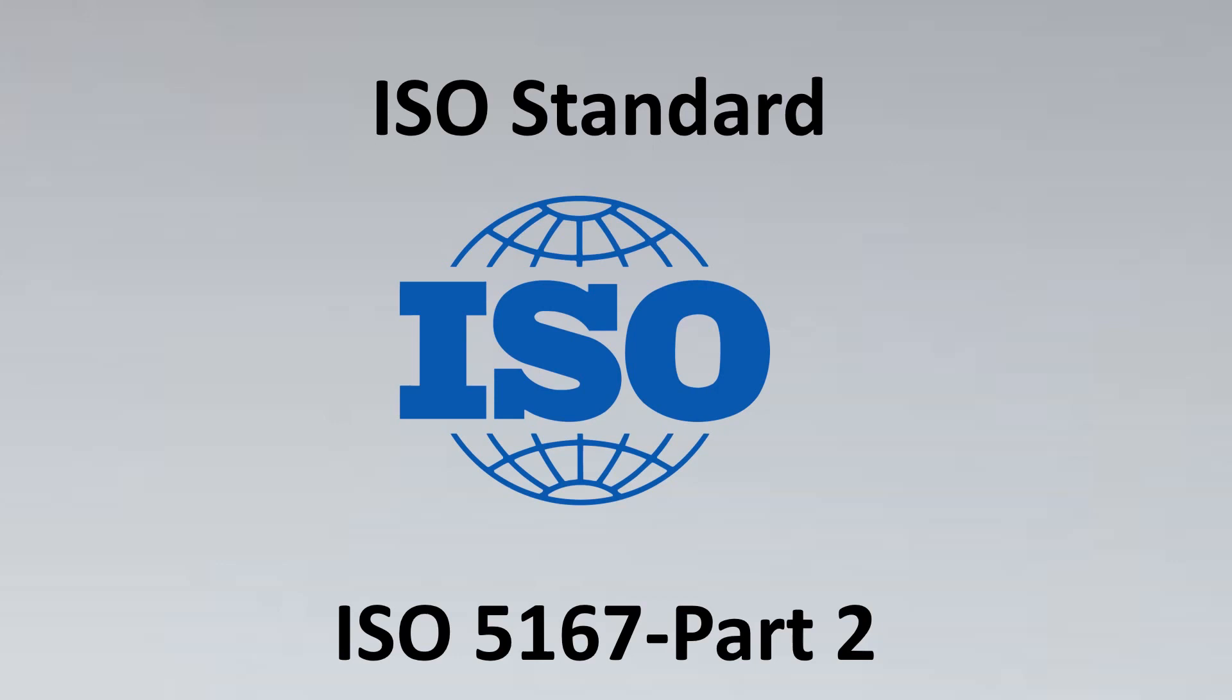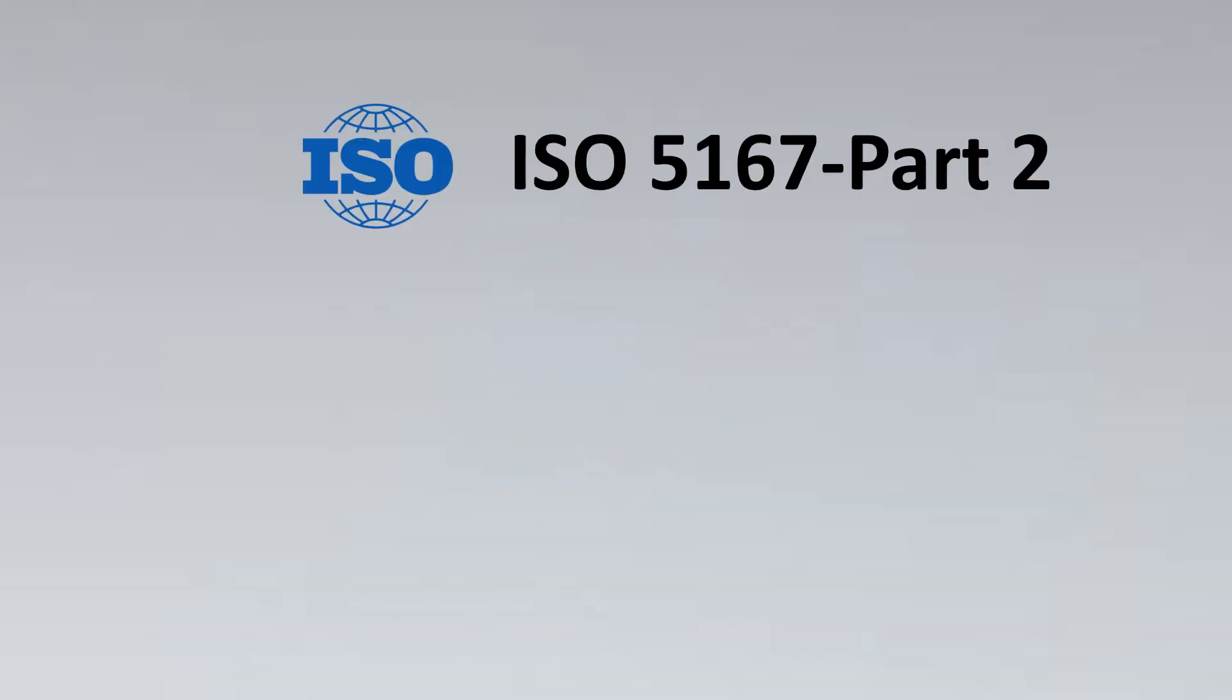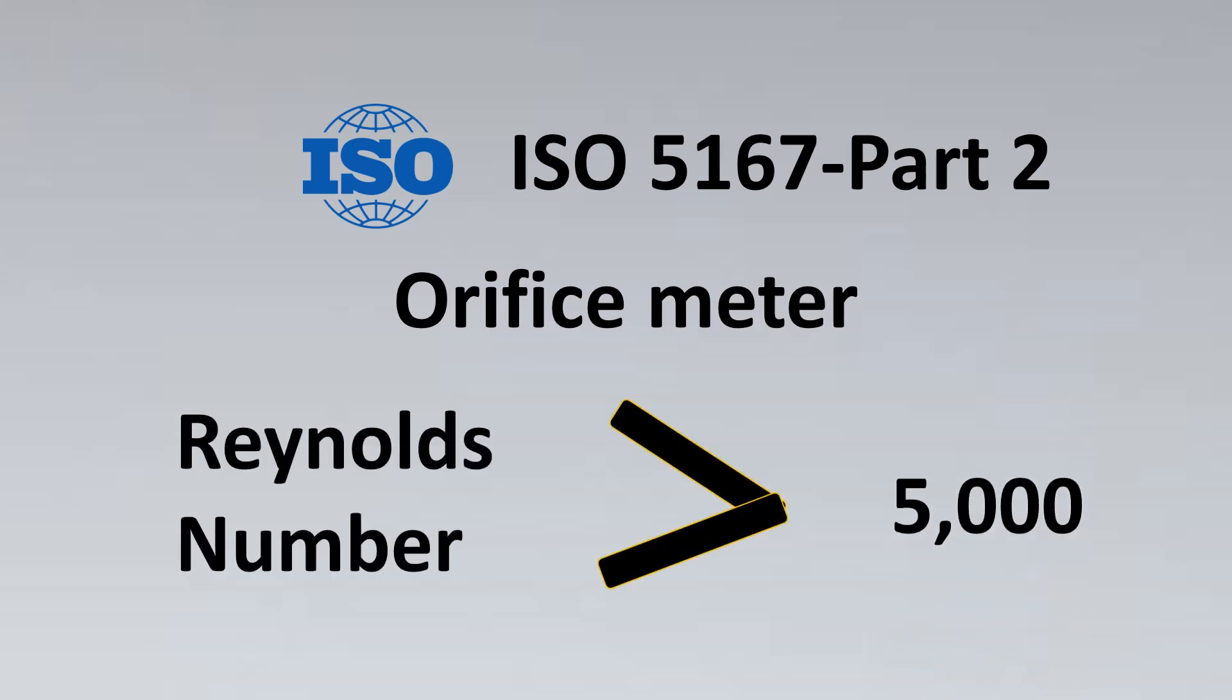And this standard has an amazing observation. It states that the orifice meters should have a Reynolds number that should be greater than 5000. Note that Reynolds number is a dimensionless number. It has no units to it. So if you see here, this 5000 is the minimum criteria if you want your orifice flow meters to comply with this world renowned standard ISO 5167. So if in your application, your Reynolds number is lesser than this, then you might not be able to go for orifice flow meters and you should go for some other flow meter technologies.